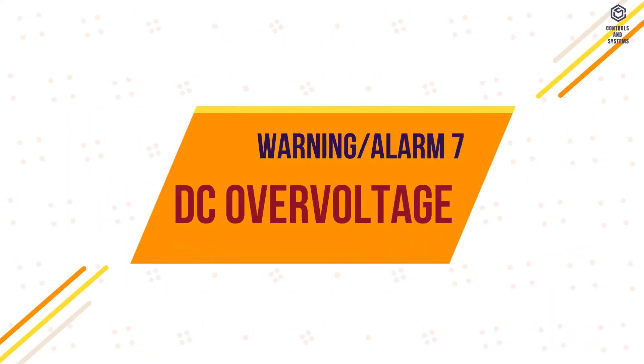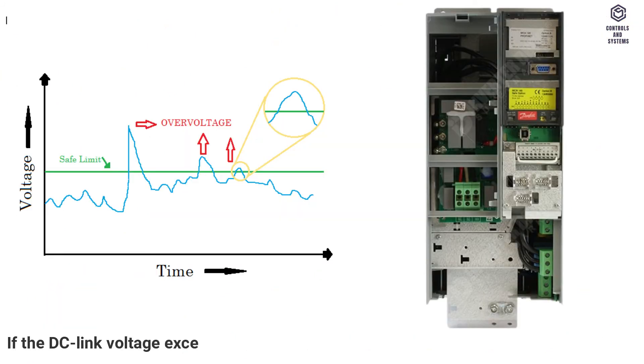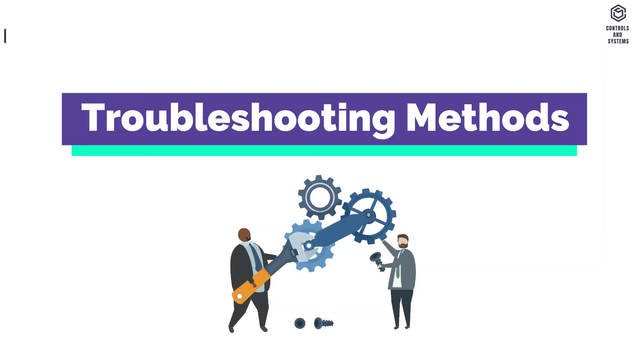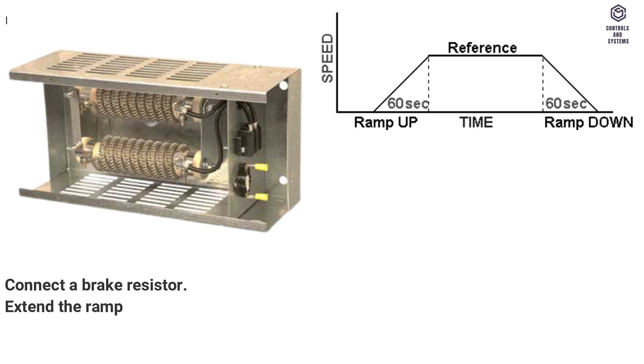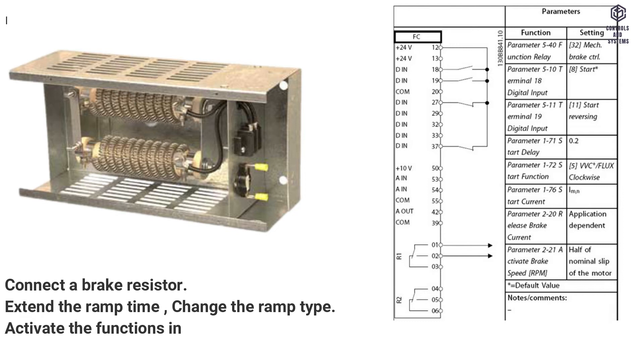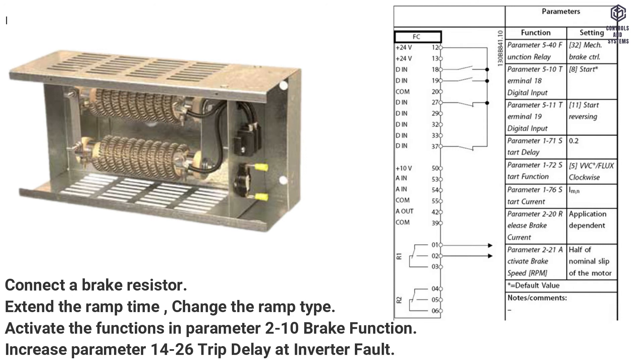Warning, Alarm 7, DC Over Voltage. If the DC link voltage exceeds the limit, the frequency converter trips after some time. Troubleshooting methods: Connect a brake resistor. Extend the ramp time. Change the ramp type. Activate the functions in parameter 2-10 brake function. Increase parameter 14-26 trip delay at inverter fault.